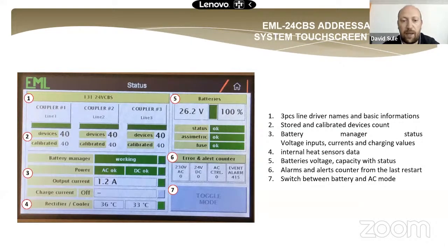On number 6, we can see an error and alert counter. How many AC230 power failures were there since the last restart? How many DC 24 volt errors? How many AC control messages came from the sub-DBs? And what is the quantity of all of the alarm events?